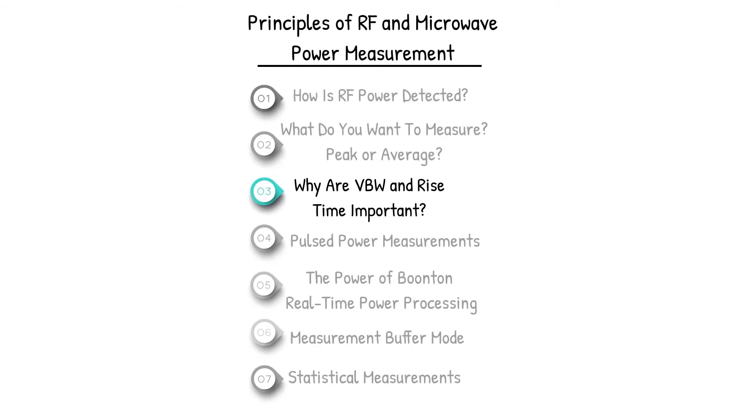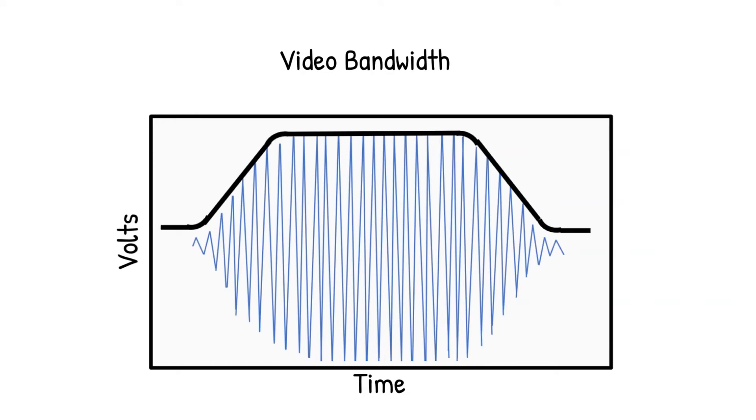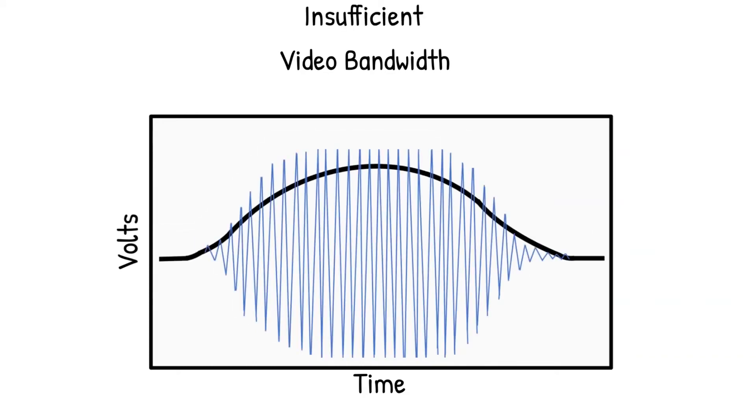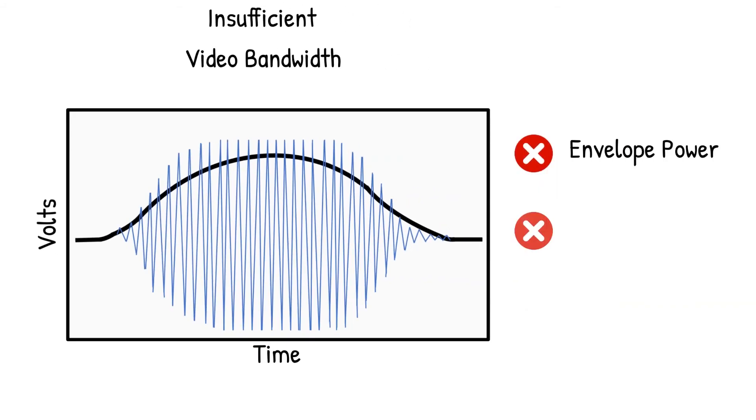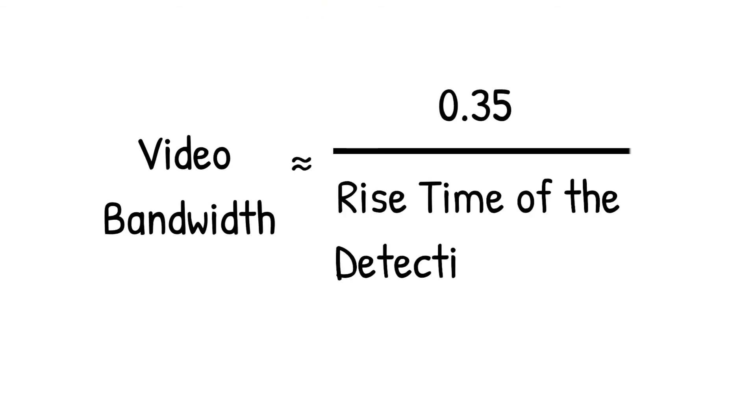Video bandwidth describes a sensor's ability to track envelope power. An instrument with insufficient video bandwidth will negatively affect the accuracy of envelope power, peak envelope power, and average power. And video bandwidth and rise time are inversely proportional.